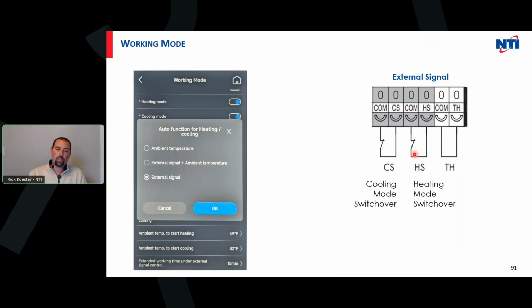But it's going to allow us to say, all right, I'm in heating mode, one zone's calling or 5, doesn't matter how many they have. It's going to now tell my machine to go on, and I'm going to target my buffer tank temp, which we'll take a look at. But all of that is done through a dry contact, or what we call an external signal. And those are your temperatures right there and the ranges.